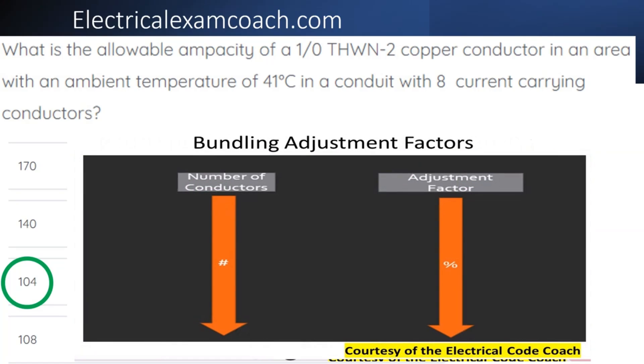Then we're going to head to our bundling adjustment factors table. We're going to start on the left-hand side and find our number of conductors, then come over to the right and find our adjustment factor.